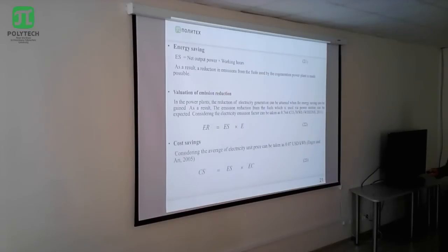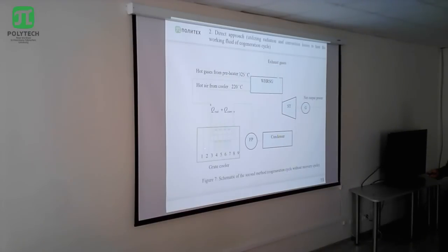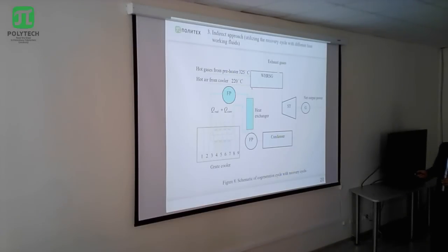We have an additional process here where the working fluid goes to the clinker and then to the waste heat recovery steam generator, because we have losses from radiation and convection here. This is the indirect approach, where we have a recovery cycle to capture the waste heat from the clinker cooler, and then a heat exchanger to transfer the heat from the recovery cycle to the Rankine cycle.